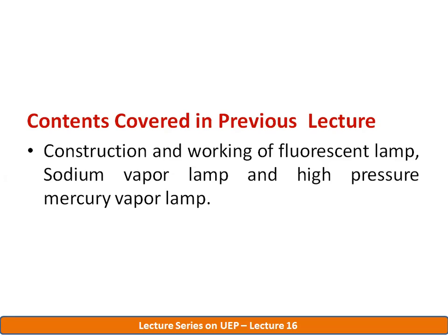The fluorescent tube consists of two tungsten filaments, coil-shaped, with electron emission coating, in circular shape. The tube is made from thin glass, and white phosphor is coated inside the tube, and it is filled with argon gas, and mercury in powder or solid form. The starter basically consists of a neon lamp as well as a bimetallic strip. Without the starter, it is impossible to start the fluorescent lamp.